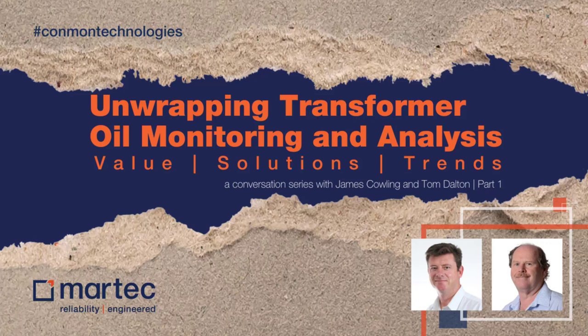And then we can also go down to temperature. Historically, people had a gauge mounted on their transformer, and a technician or an engineer or the substation staff would have to walk to the transformer and go see what the top oil temperature is or the winding temperature. Technology's moved on, and we've got newer technology where we can install permanent electronic temperature monitoring sensors on the transformer that can be connected to SCADA or DCS. And we can even then take some smart sensors. For example, we can combine a hydrogen sensor with the temperature monitoring system to give a very cost-effective solution.